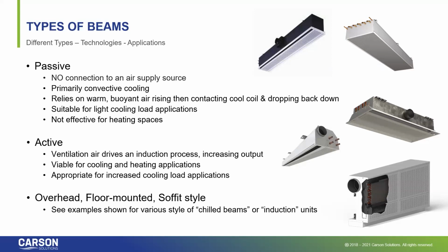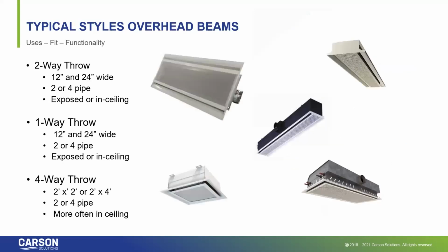On the other hand, active chill beams are activated by a primary air source being delivered to the beam that creates a venturi or an induction process, which helps with increased cooling loads and is certainly a viable option for heating applications as well. In the right-hand corner is a floor-mounted chill beam, and there are other styles such as soffit chill beams as well.